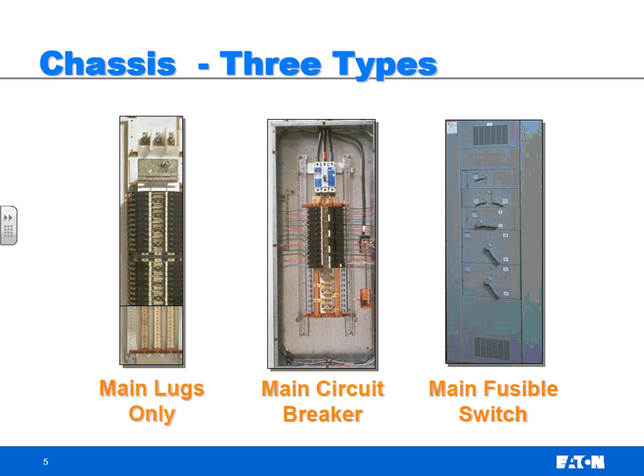But when you're talking a low energy short circuit, fuses can be, I'll call them, inherently dangerous, because it can sit there for a long time letting the power flow through, waiting for that copper inside the fuse to melt. Now a circuit breaker on those low levels is going to work much quicker and take the circuit offline. So in those instances, your circuit breaker is going to be much more safety conscious than a fuse.